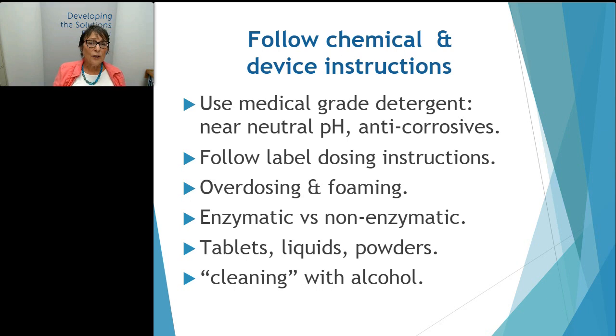And then I'd like to comment on cleaning with alcohol. This is a tricky one because sometimes it's actually in your instructions for use. You may have a device that actually says clean with alcohol. One reason why this happens is because instructions for use may be written by an engineer. This is a person who knows nothing really about the cleaning process. They only know about their device. And they're using isopropyl alcohol as a fallback because they don't really know what else is out there. Isopropyl alcohol, or any type of alcohol over 50%, is really not a cleaner. It's a great disinfectant, possibly, depending on how it's prepared, but it's not a cleaner.